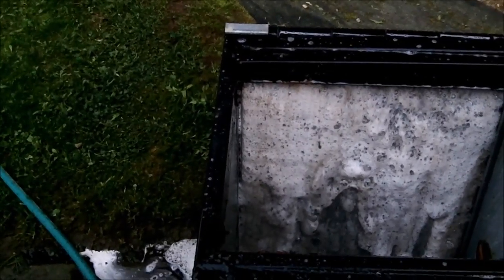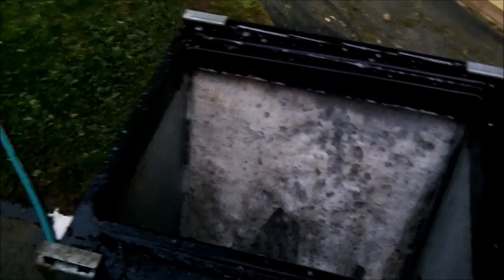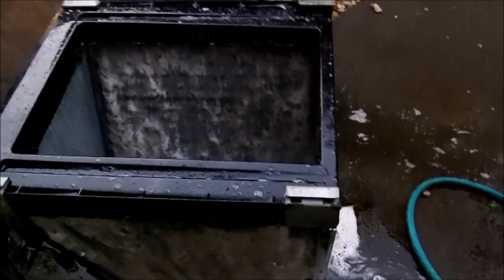It's getting pretty dark but I've already washed one coil. I kind of changed my ductwork analysis - I started messing around, went back to the coil and the number one looked pretty clean on the bottom but it was packed full of dirt. I tried to wash it and clean it in place and that just did not work. So I had to actually pull it and clean it. Now I'm on the outdoor side of the 5-tonner and there it is, so I'll get that thing washed out real good.